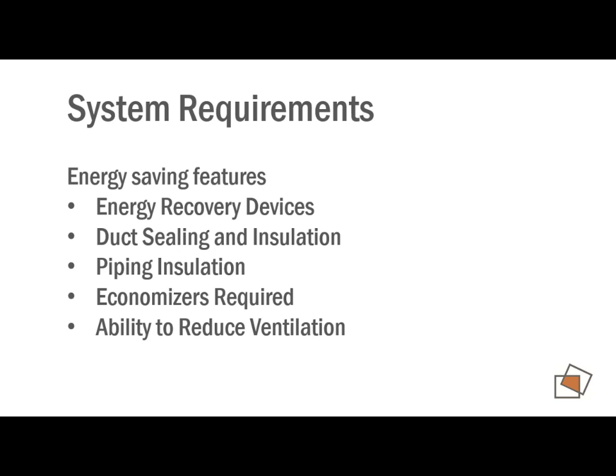So it's interesting because in the 2015 code, they moved that threshold to 5 tons, which is more of your typical maximum furnace size. So the idea was they moved it to where if you're just designing split systems, you're not really required to have an economizer. So that may be something that's addressed before we go to the new code adoption in Springfield. But right now, as it reads, 3 tons and up, you have to have an economizer. So you'll have to give us MEP engineers some space for a louver, because now that's 1,200 CFM we've got to bring in through the wall or the ceiling or something like that.